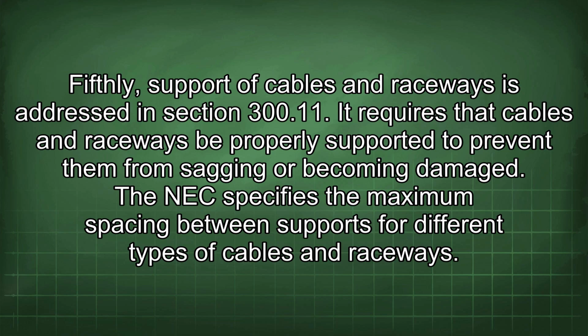Fifthly, support of cables and raceways is addressed in section 300.11. It requires that cables and raceways be properly supported to prevent them from sagging or becoming damaged. The NEC specifies the maximum spacing between supports for different types of cables and raceways.